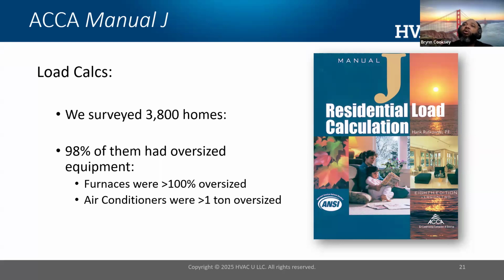We conducted a study here locally in Michigan and we surveyed about 3,800 homes. And when we looked at those 3,800 homes, 98% of them had oversized equipment. The furnaces themselves, when we did the survey, were oversized by 100% or more. And the air conditioners that were installed were oversized by 1 ton or more, which represents a number of issues: inefficiency, rapid starts and stops, mechanical failures, breakdowns, and your bills will climb due to the inefficiency. So as a result, we have this problem. If you replace a combustion appliance with a heat pump and you don't do your due diligence for design, you're going to set that customer up to have a bad outcome.